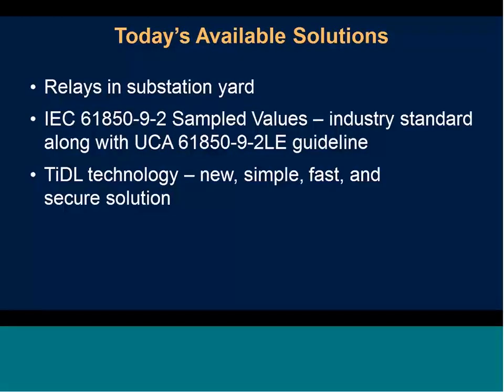We're going to talk about three solutions that can be used to implement this digital substation concept to varying degrees. The first is just putting the relays in the yard, similar to what we mentioned earlier, with the key difference being a communications link back to a central location. We'll also talk about the 9-2 sample value solution, specifically the light edition or 9-2 LE guideline from UCA that's used by most manufacturers to make an interoperable solution. And then last, we'll finish up with time domain link, or TiDL technology, which is a new, fast, easy to install and simplified solution.